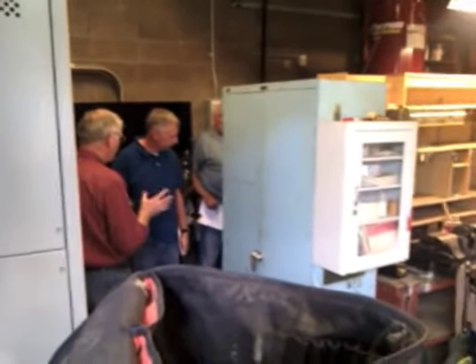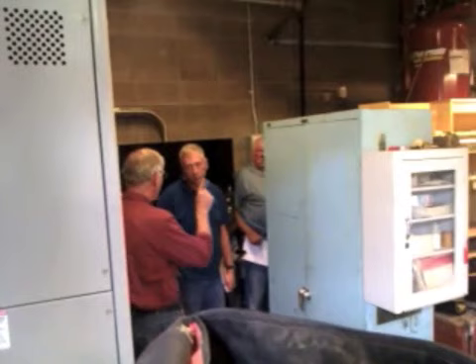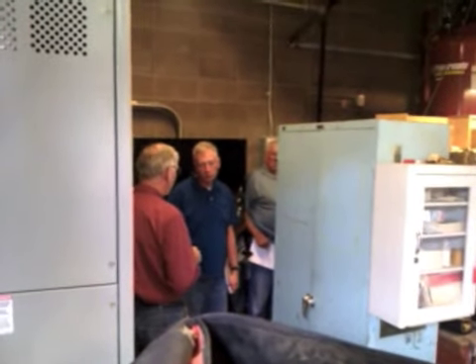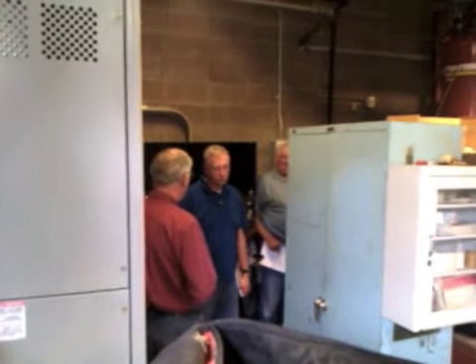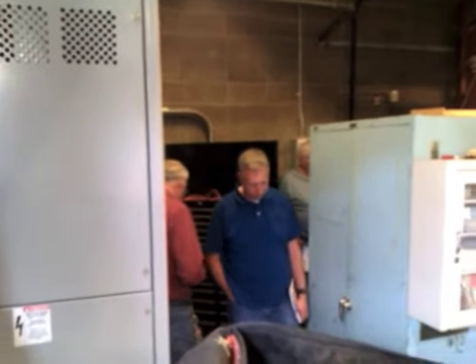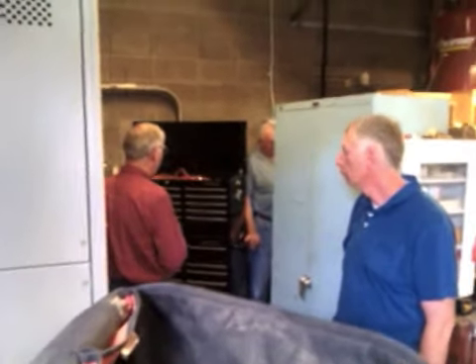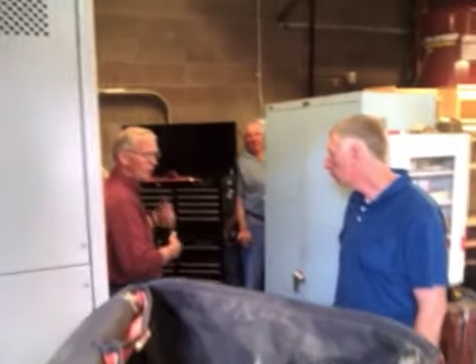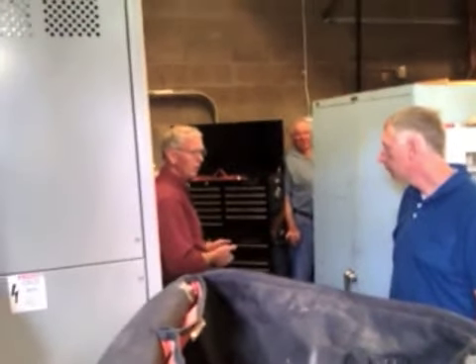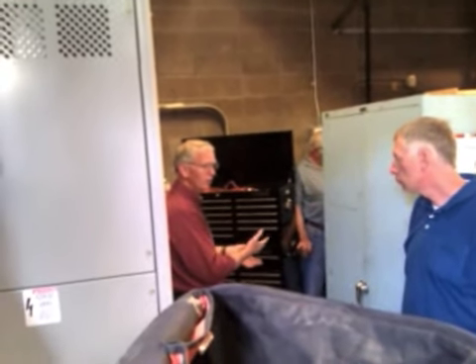The bid they gave us will include disposal, taking all this out and putting those tanks in, putting the variable frequency drives, and replacing two backflow preventer valves in the other room — one of them is for sure bad right now. One of the main two-inch brass valves is also bad and we're going to replace that. They would also put a different level control on our aeration system next door, and that would be used to tell the pumps when to come on.